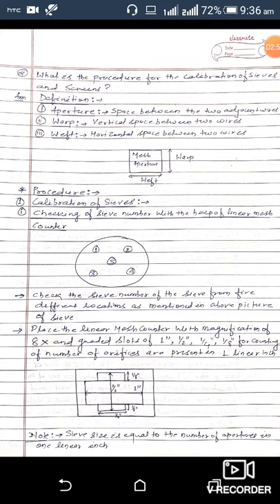The procedure for calibration of sieves: the first point is checking of sieve number. With the help of a linear mesh counter, check the sieve number from five different locations as mentioned above. Place the linear mesh counter with magnification of 8x and a graded slot of one inch, half inch, one-fourth inch, or one-eighth inch for counting the number of orifices present in one linear inch. Note: sieve size equals the number of apertures in one linear inch.